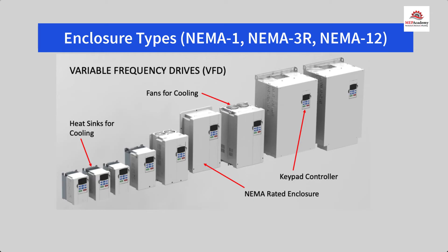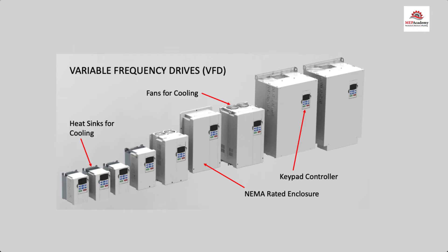Since VFDs produce heat during operation from the semiconductors, this must be part of the consideration when selecting a ventilated enclosure versus a cooled enclosure. Avoid locating a VFD on a heated wall or in direct sunlight.